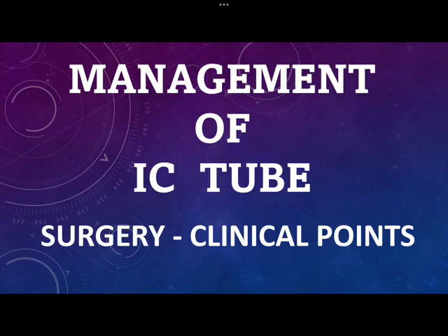If this water column is 20 cm high, minimum bubbling in this 20 cm water column means we have applied negative 20 cm H2O pressure to this chamber. And that is going to get to the lung. Understood? That is the concept.